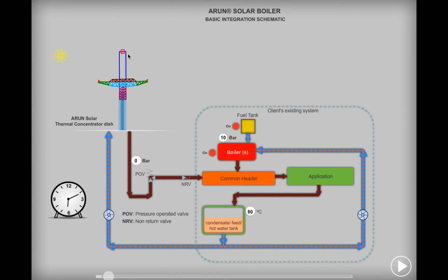The steam generating system consists of the Arun dish system, pumps, valves, etc. Once the system starts generating steam, the pressure in the line starts increasing. Once this pressure matches the pressure in the existing boiler header, a valve will open and steam will be delivered to the common header. This process will continue whenever the Sun is available.